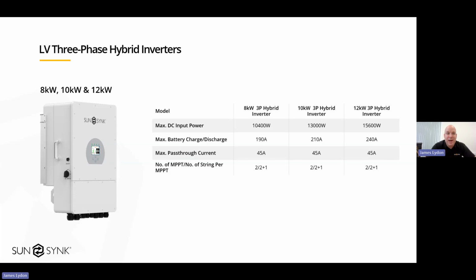Okay, 3-phase. So we do an 8, a 10, and a 12 kilowatt. So these are low voltage. So when we say low voltage, that's referring to the batteries that they will work with, that we'll come on to in a minute. So yeah, we do an 8, a 10, and a 12. And all of our low voltage inverters, you can easily parallel up to 12 of them together.